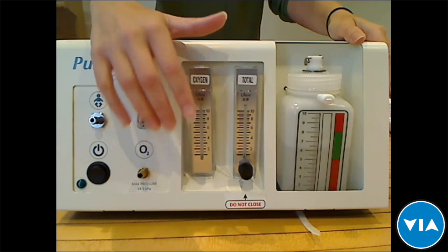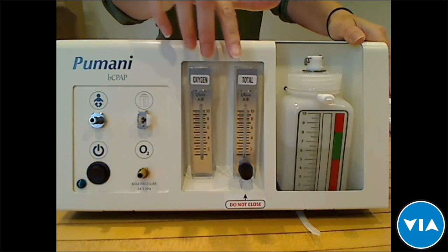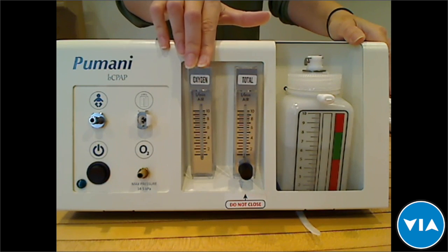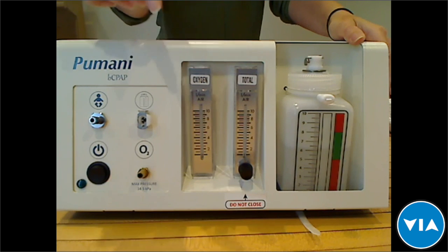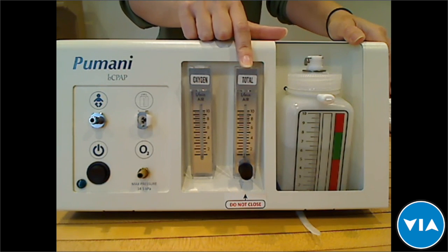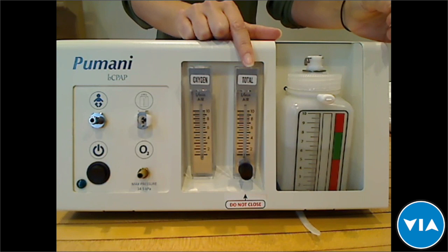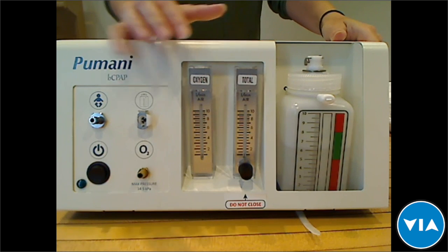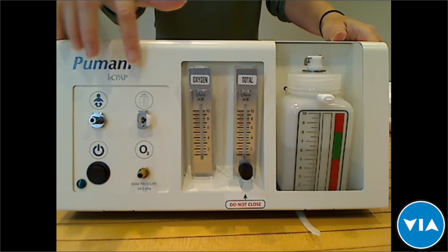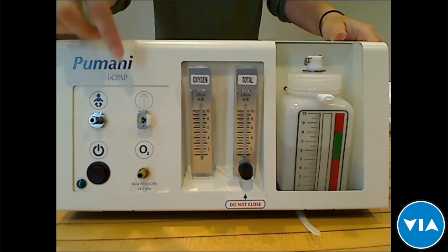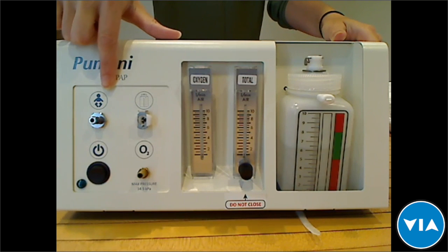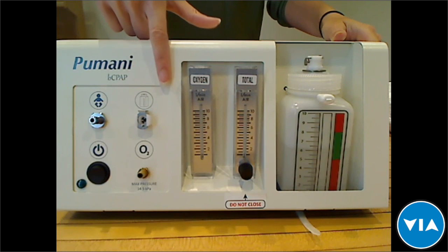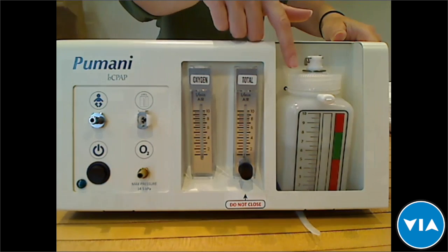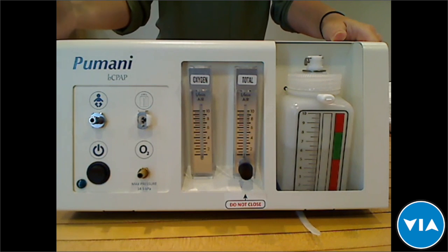On the front of the machine, you also have two flow meters. There's an oxygen meter that reads the oxygen flow, and a total flow meter, and that is the total flow that's being delivered to the baby. And then on this side of the machine, we have four controls. There's a baby port here. That's where the tubing to the baby goes. This is the bottle port, so you'll have tubing from here to the bottle, which I'll demonstrate in a moment.